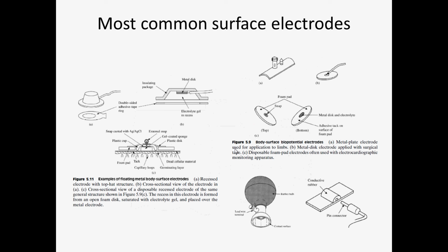Anyway, so those are the most common kinds of electrodes that you're probably going to use. Some of them are rubbery electrodes, like this one, mostly used for stimulation. Skin electrodes for EMG, ECG mostly present like cups, where the metal disc doesn't touch the skin directly, but there is a sponge filled with some electroconductive gel or paste, or you actually fill it by yourself before performing the recording.